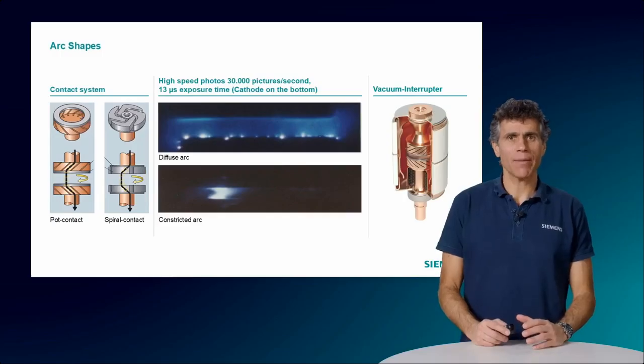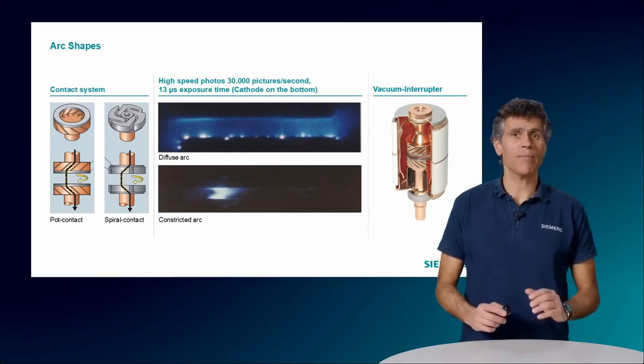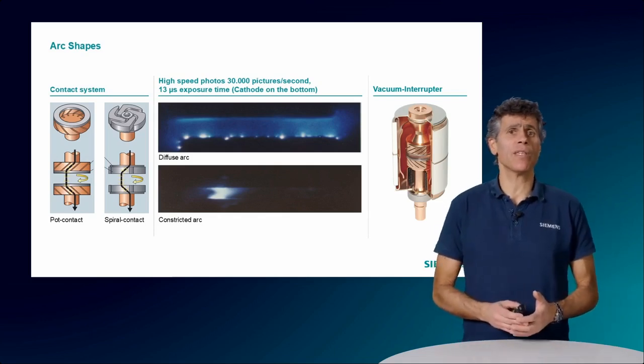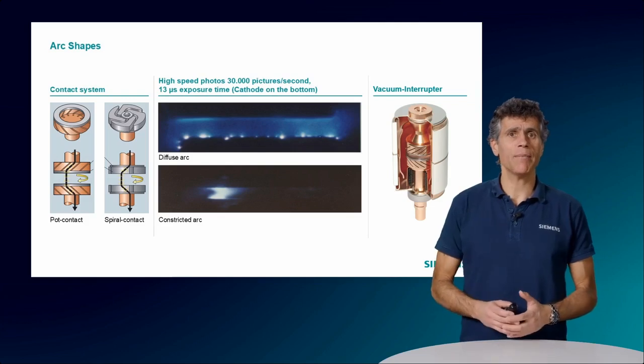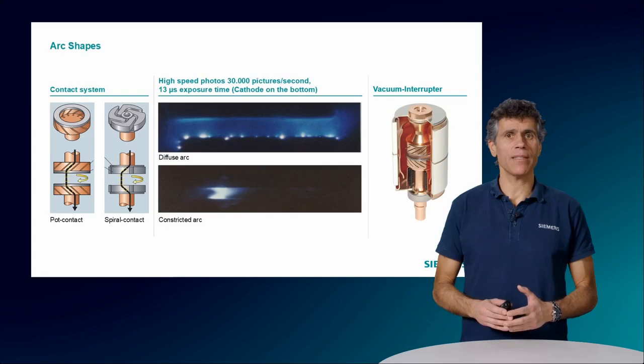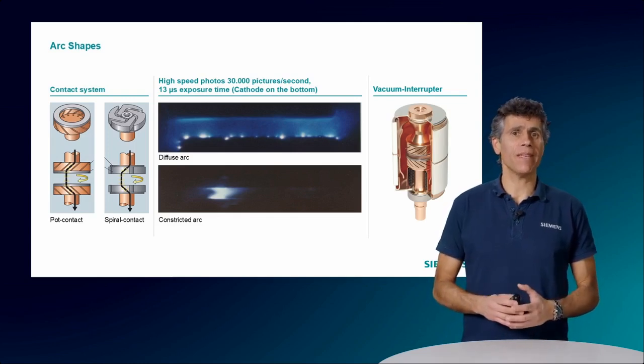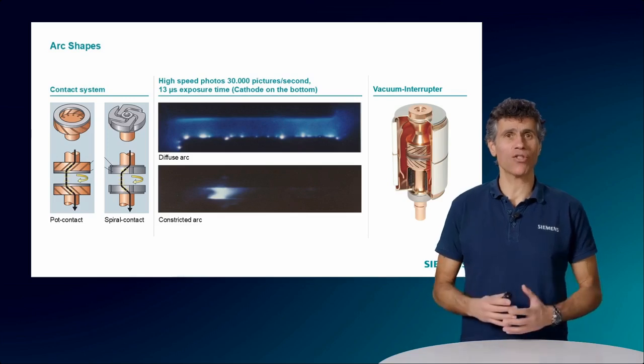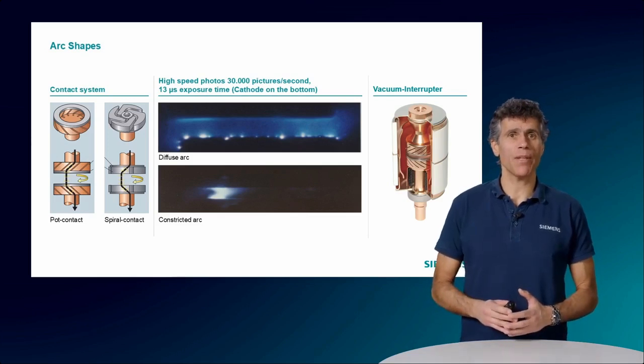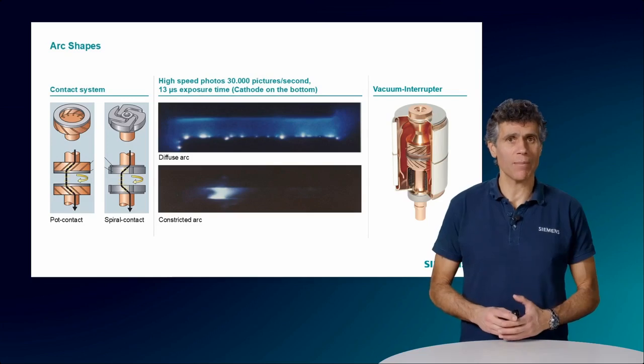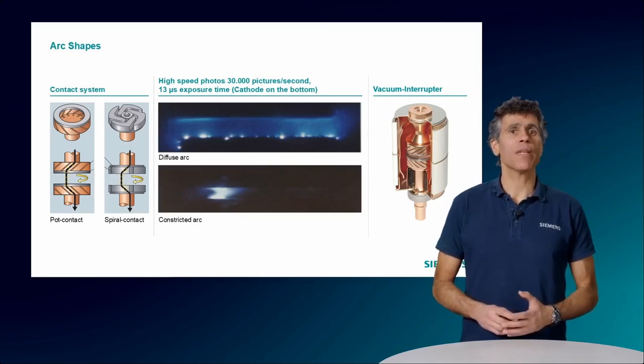If we cut the cable of a running motor, we would see a sparkle, an arc. We don't do that because the consequence would be an arc, and that can be dangerous. Instead, we use a switch so that the arc takes place in a controlled and safe environment. That arc can go from invisible to a huge lightning strike, potentially harming people and damaging equipment if not properly managed. So it's nothing to play around with.